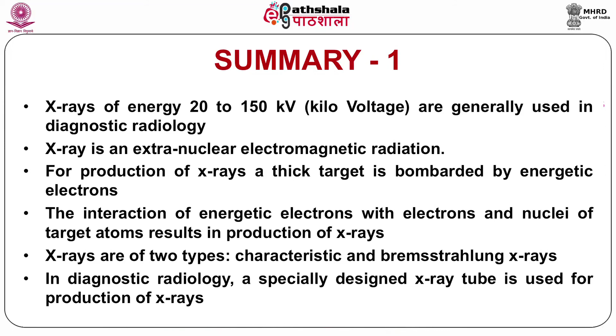In diagnostic radiology, a specially designed X-ray tube is used for production of X-rays. In diagnostic radiology, tungsten, rhodium and molybdenum are commonly used as target materials for production of X-rays, and the majority of the energetic electron energy is converted into heat and only a small fraction is converted into X-ray energy. The characteristic and energy of the X-ray spectrum depends on the choice of target material and energy of projectile electrons.